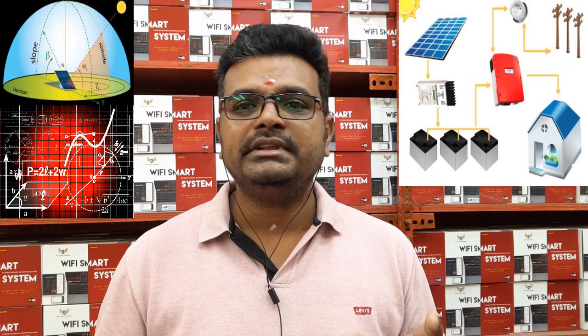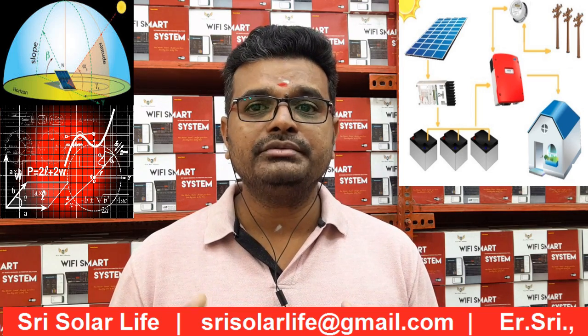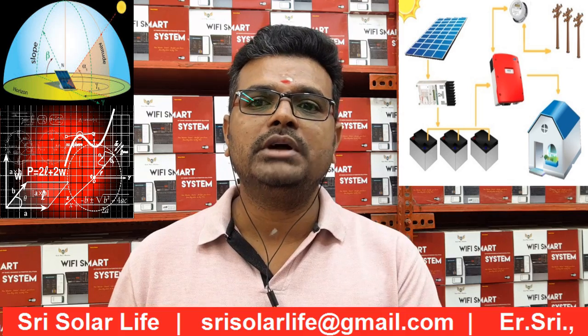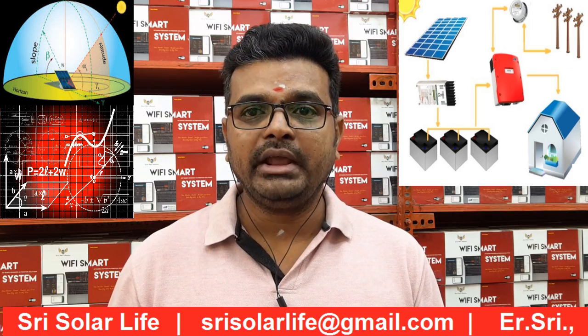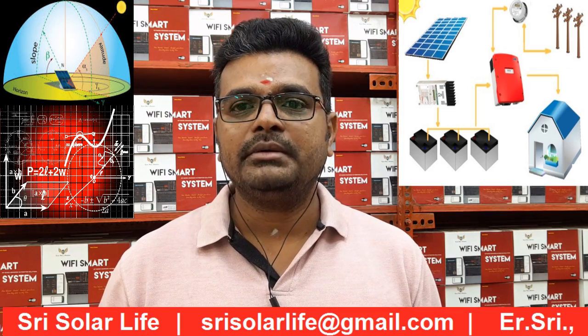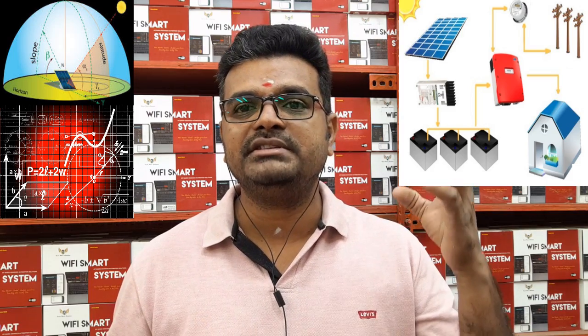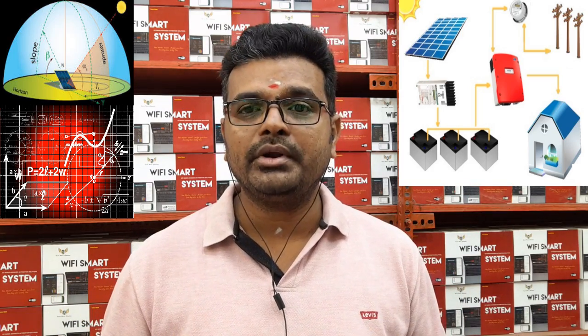If you want to store energy in a backup battery system, you have to check the battery characteristics and technical specifications, including losses, aging factors, and temperature ratings — whether you place it indoors or outdoors. You also need to calculate the autonomy: one day, two days, or three days. Increasing the number of autonomy days means increasing the number of batteries in series and parallel. You must also check the depth of discharge (DOD) and the charge and discharge levels from the solar panel to the load.